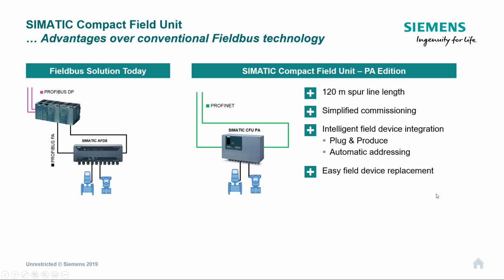This really is one of the weaknesses of the conventional Profibus PA system, where you're using a manufacturer GSD in your hardware config. So we've all been there. Working for Siemens, and we got a brand new pressure transmitter. It does all of this stuff. You put it into your project, and then the supplier of the instrument says, "Well, you need a new GSD." And if you haven't got something like configuration in run, which the Compact Field Unit also supports, by the way, then you'll have to download that new GSD into your PLC or your automation station, and a lot of times you have to put that into stop. So you're actually waiting for some planned shutdown so you can just change an instrument, which is ridiculous.